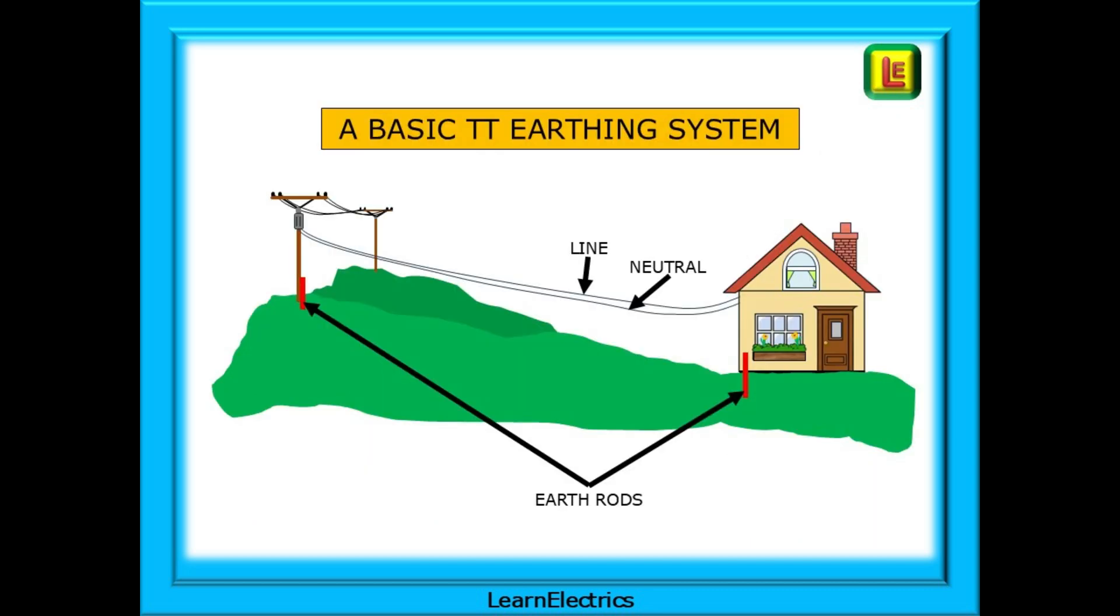A quick recap on TT systems will help. We have the supply cables, usually on overhead poles, but not always. There will be a supply transformer and fuses mounted on the poles, and a line and neutral will be taken off to the dwelling. There is no copper earth connection between the pole and the dwelling. Instead, an earth rod is installed at the pole and at the property.